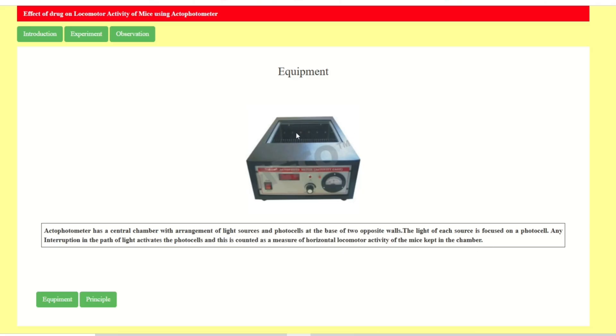This interruption is counted as a measure of horizontal locomotor activity of mice kept inside the chamber. The light is constantly passing through to the photo receivers. When you put an animal in the chamber and it moves, the beam is interrupted, and the photo cell receivers count this — measuring horizontal locomotor activity.